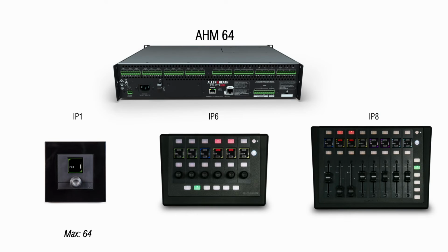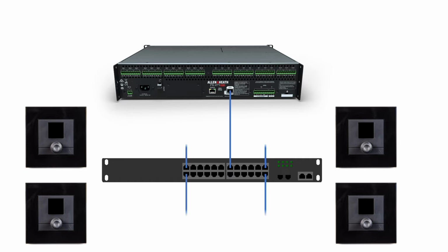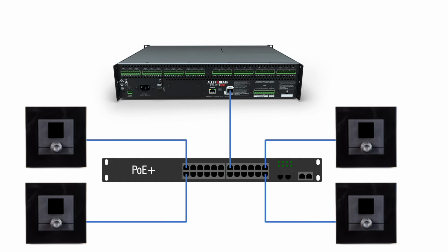A maximum of 64 IP1 controllers, 16 IP6 and 16 IP8 controllers can be connected to AHM64. 32, 8 and 8 for AHM32, and 8, 2 and 2 for AHM16. Devices can be networked using a standard unmanaged network switch.